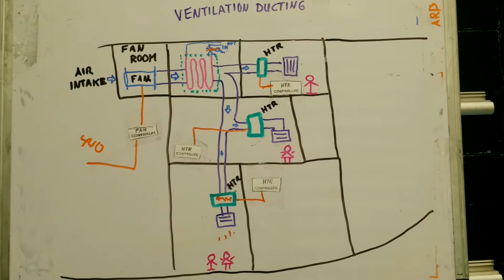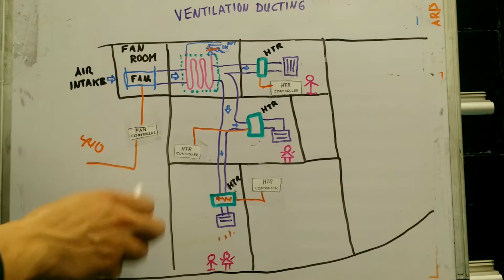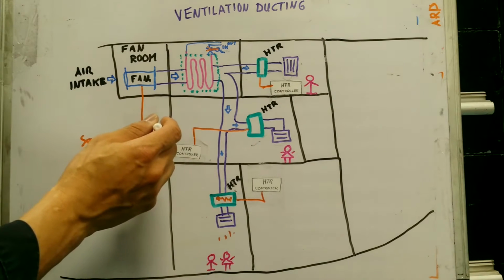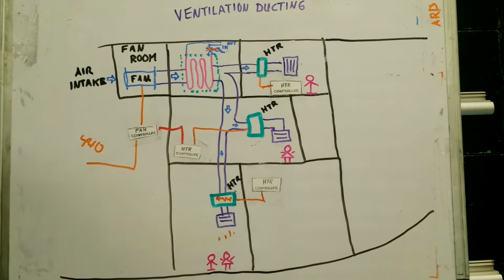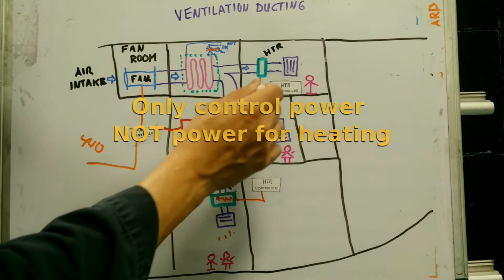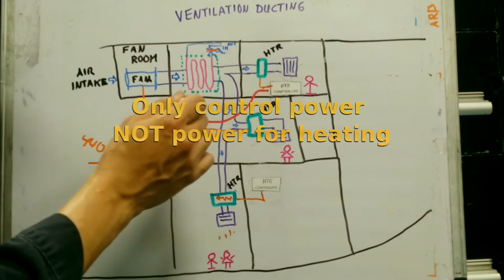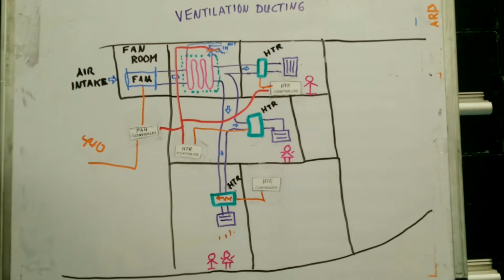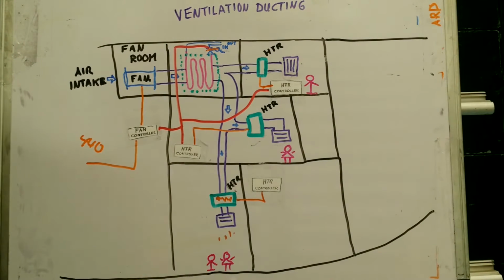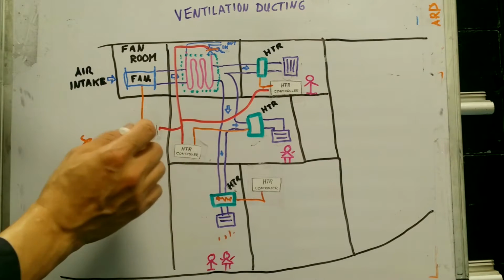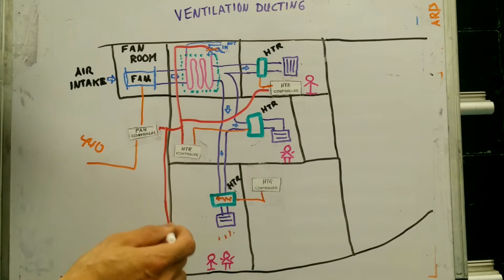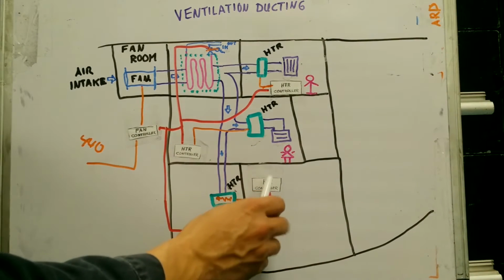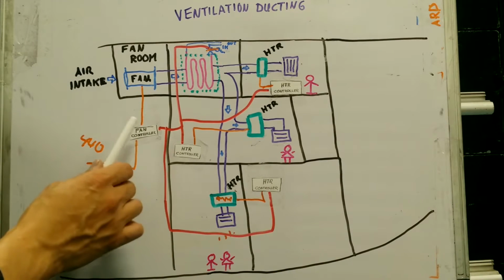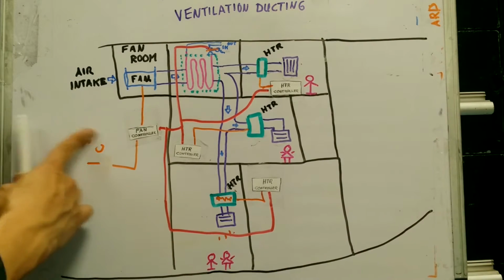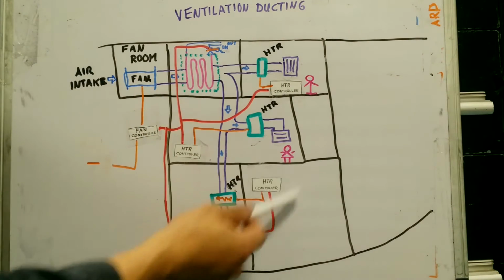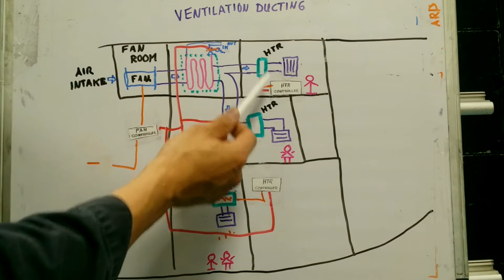But the fan controller is going to have a step-down transformer that is going to provide 110 volts control power. That 110 volts will give power to all of the heater controllers, and that also will energize the solenoid valve. What I'm trying to represent here is that the red power lines come from the fan controller, and that is 110 volts for the control side, for the reheater controller. If we lose power over here, so our fan controller doesn't get power, we lose control power in all of this. We will not have cooling, nor will we have heating.